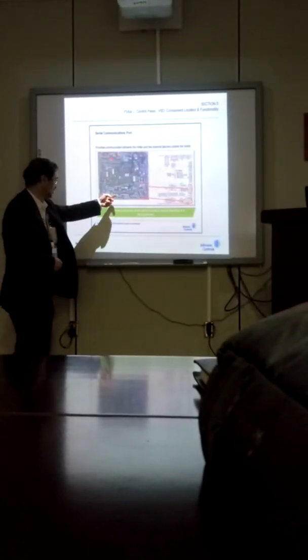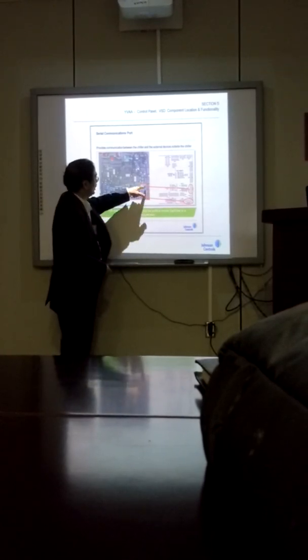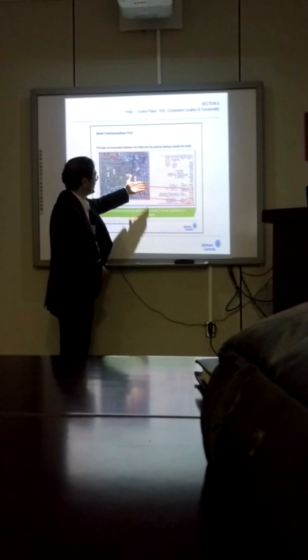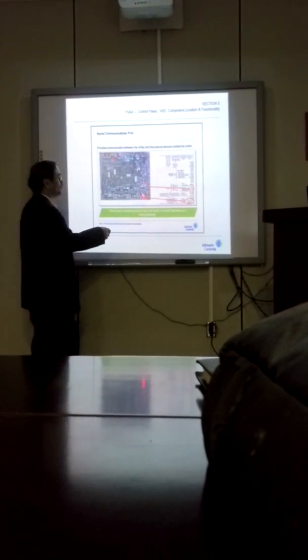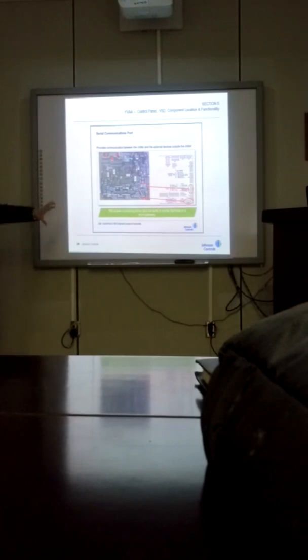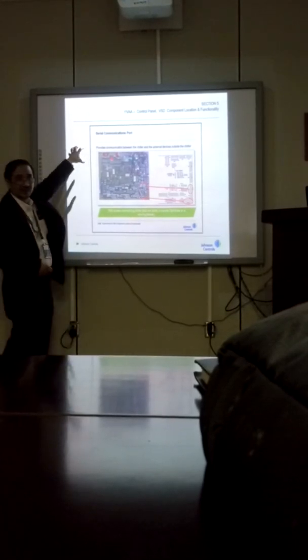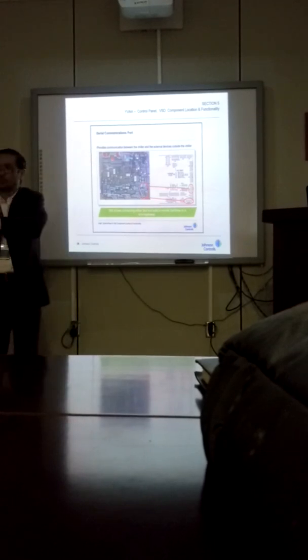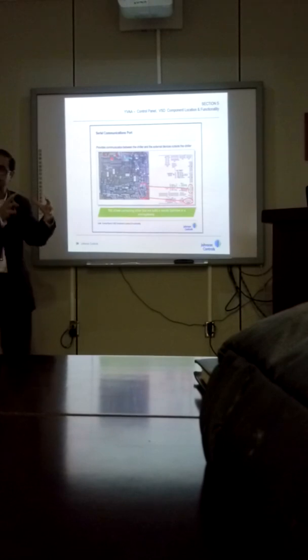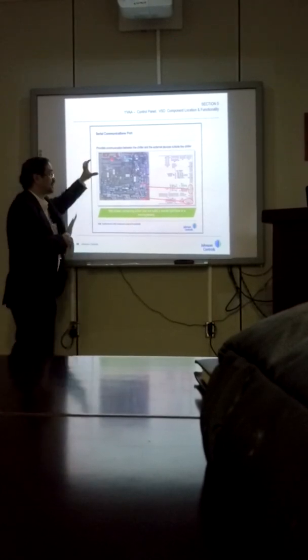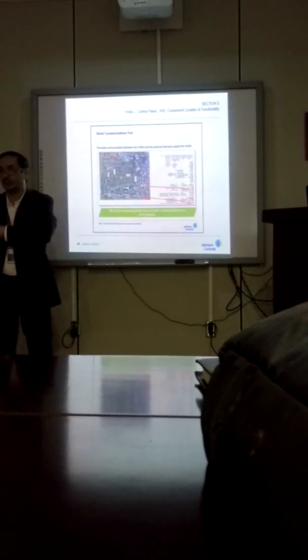So all of the data is inputted here, like the analog signals. What are the analog signals? These are the pressure transducers, temperature sensors, suction, oil, discharge, HPCO, and many other things. These are the inputs. System 1, System 2. These are other things which we can connect, like a mobile printer here. This is a communication for on-off BMS. But if you need a BMS system, you need an E-link, to collect all the data in your computer. So you need an E-link to translate our protocol to your protocol, whatever you will use.